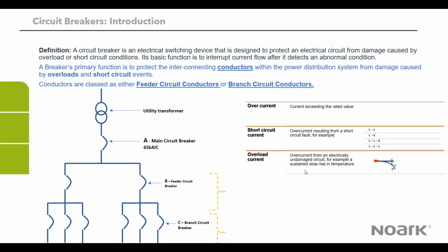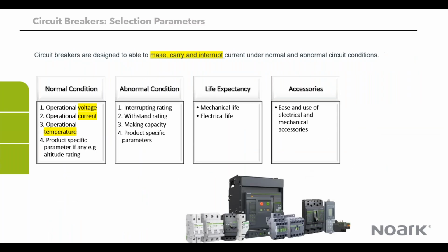And so if it gets to a particular threshold, then it's going to cause a trigger. So basically it's an inverse time function. It's a function of how long the circuit is exposed to that overcurrent, because it's a small amount over the rated current. So the longer it's exposed to it, the quicker you're going to get a trip on the circuit breaker.